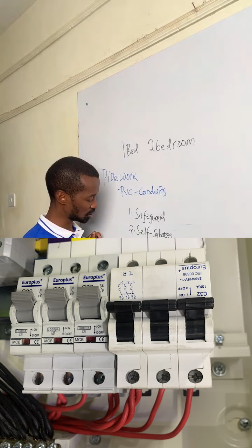Majority of electricians conduct an electrical installation but refuse to do ceiling pipework properly. At Topites Electricals and Electricians, we ensure we take ceiling pipework seriously, because in the ceiling, temperatures are usually very high, which makes the insulation on the wires soften. This may even lead to the insulation coming off, especially for people who are fond of using insulation tapes or that button connector.